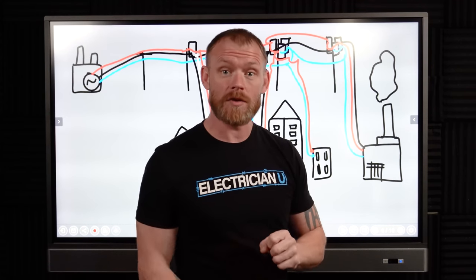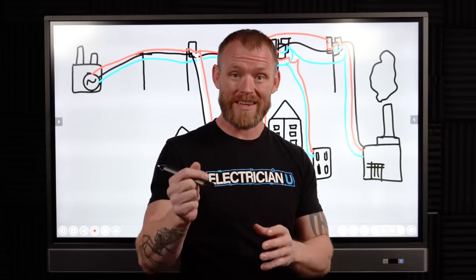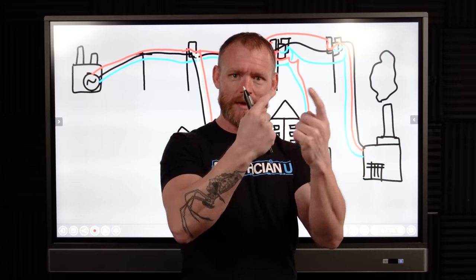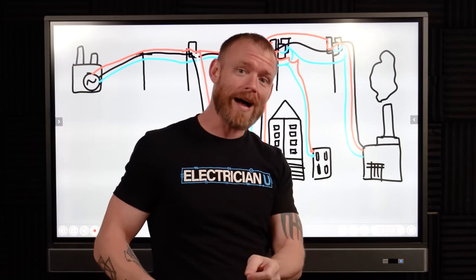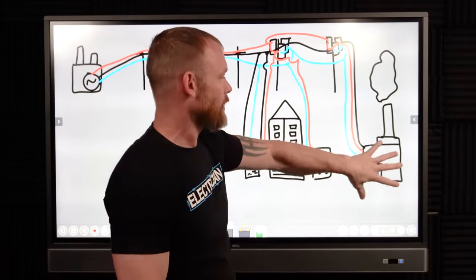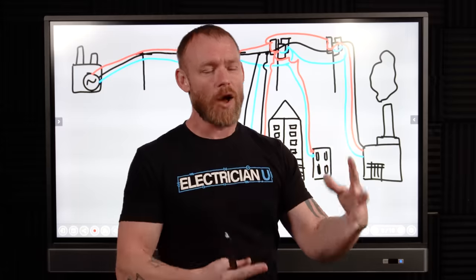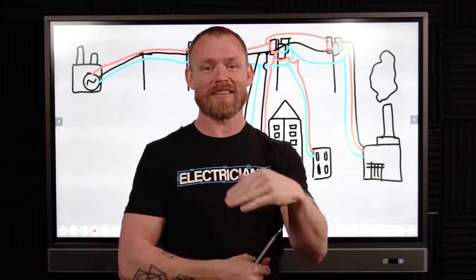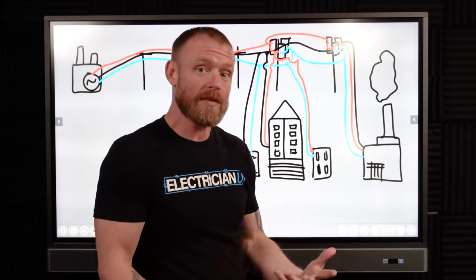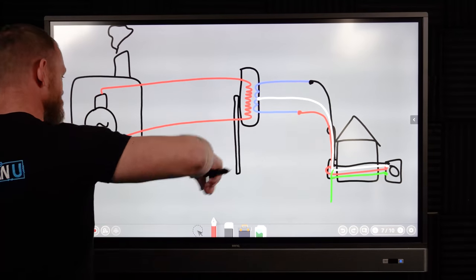There are grounded systems and ungrounded systems. In code, 'grounded' refers to the neutral and 'ungrounded' refers to the hot — they're both doing the same thing, like turning a light bulb on. Grounding conductors — the green or bare wire — are the equipment grounding conductors. An 'ungrounded system' means there is no grounded conductor or neutral run, because all of the equipment is running on the three phases and there's no need for a neutral.